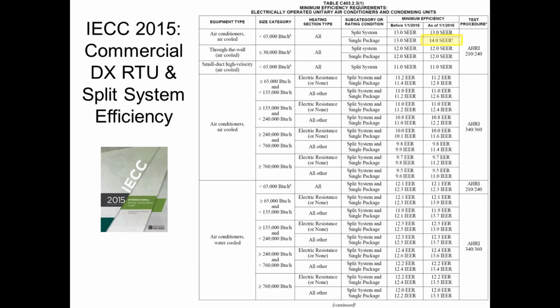So for small systems, 5 tons and under, you need to have 14 SEER as your rating point. When I get to bigger systems, 65,000 BTUs and up, I'll have a couple rows to look at. One is electric resistance or no heating. Then the other row is all other heating, which would mean gas heating in our case, or I guess it could be hydronic heating. But for most of us, it's going to be gas heating. And for today, it's going to be gas heating.